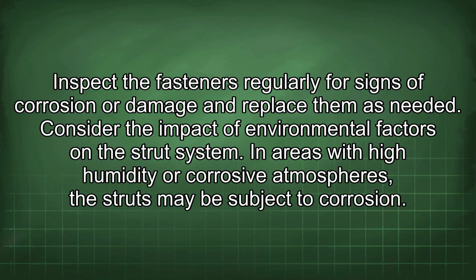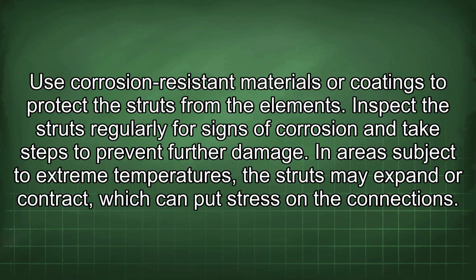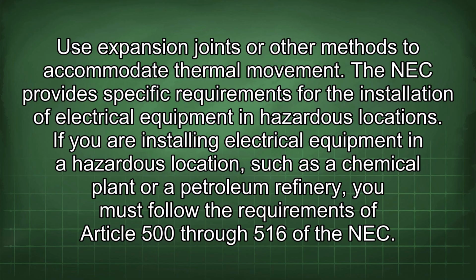Consider the impact of environmental factors on the strut system. In areas with high humidity or corrosive atmospheres, the struts may be subject to corrosion. Use corrosion-resistant materials or coatings to protect the struts from the elements. Inspect the struts regularly for signs of corrosion and take steps to prevent further damage. In areas subject to extreme temperatures, the struts may expand or contract, which can put stress on the connections. Use expansion joints or other methods to accommodate thermal movement.